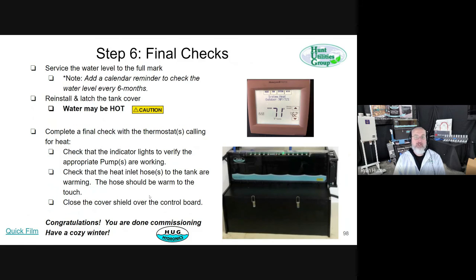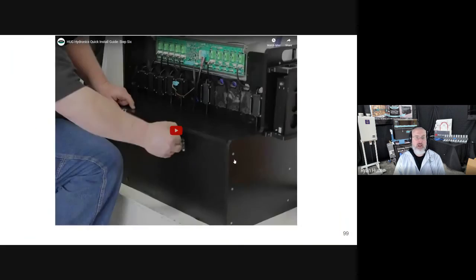All right, final checks. Now's a good time to put a calendar reminder to check the water level every 6 months. You want to reinstall the latch and complete your checks. Turn on the thermostats, make sure that the correct pumps are turning on. You've got that set right. Check the water going to the boiler, you can feel that temperature in the hose, and the hose coming off the boiler should be significantly warmer. And then close it all up.